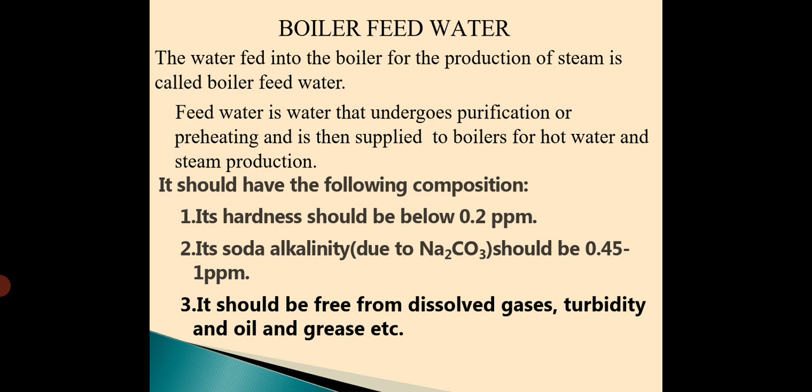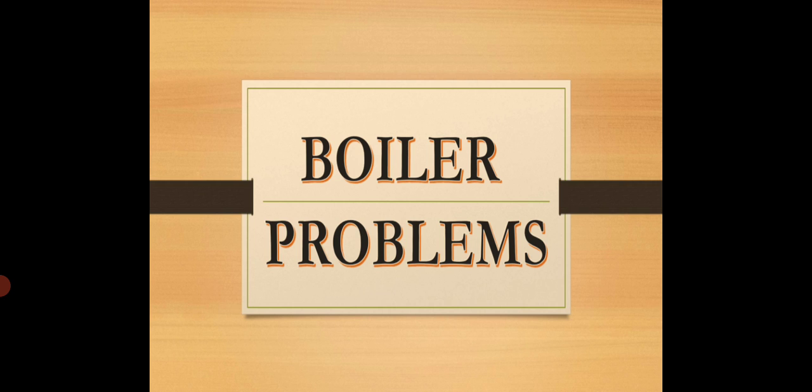Suppose if these are present - if hardness exceeding 0.2 ppm, soda alkalinity greater than 1 ppm, and if the water contains dissolved gases, turbidity, oil and grease - it may lead to certain boiler troubles or troubles inside the boiler which are termed as boiler problems. Now, let us see about the various boiler troubles which are caused due to the presence of hardness producing salts or due to the presence of sodium carbonate or due to the presence of grease, oil, and turbidity.